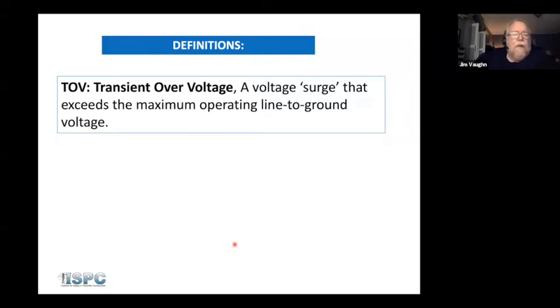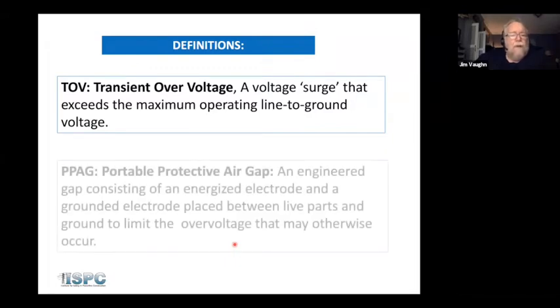TOV, let's talk about this. Do not underestimate this. Transient overvoltage is a surge that exceeds the maximum operating line to ground voltage. TOV is not a big concern in distribution, partly because it doesn't occur very often, but we also have tons of surge arresters out on a distribution circuit that prevent this TOV rise from becoming a problem for us. The other thing is that we typically in distribution are working phase to ground at 8 kV, and we're using 30 or 40 kV hose or blankets that produce a considerably higher insulation value if we properly cover up.